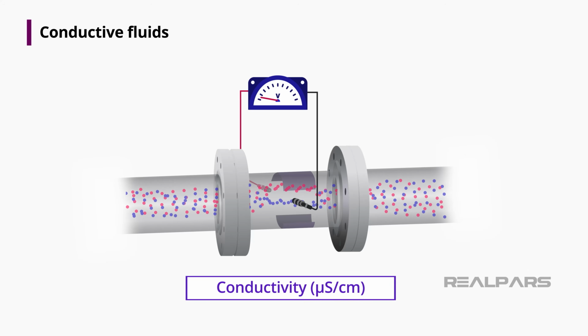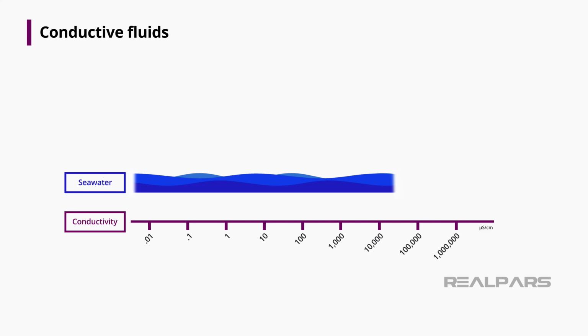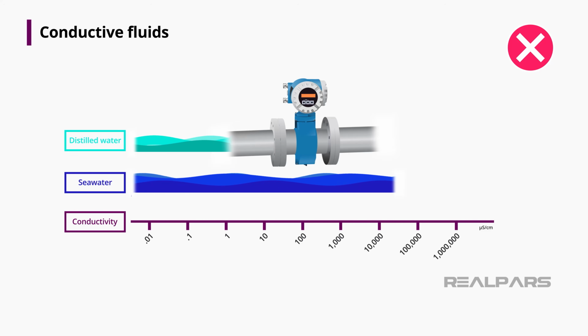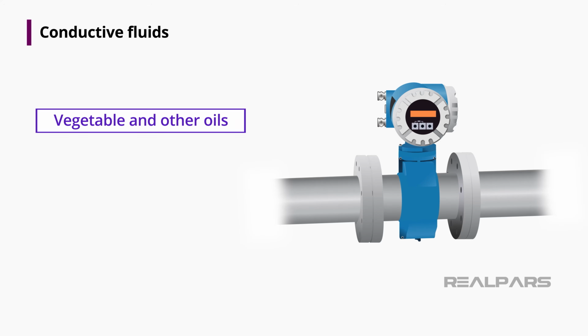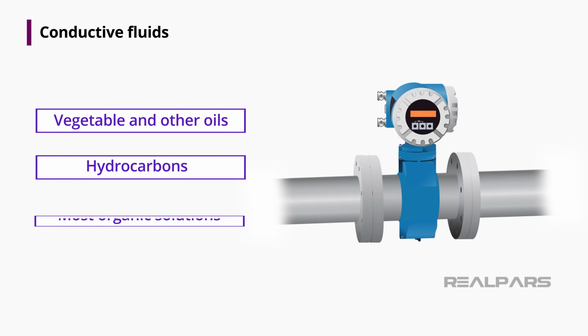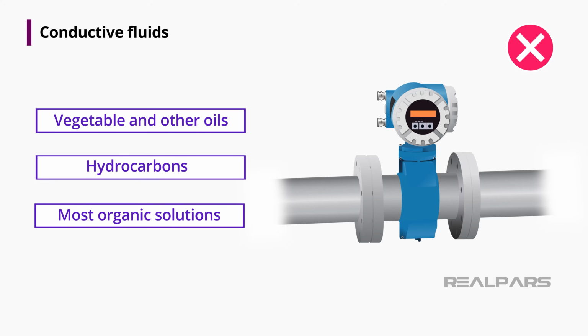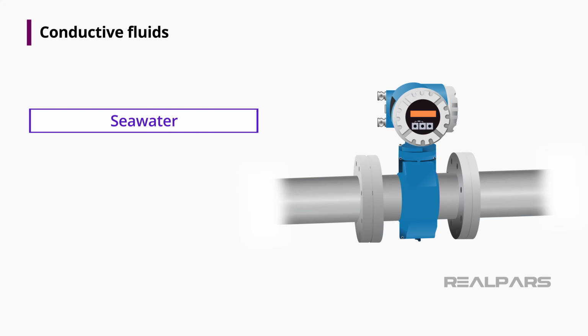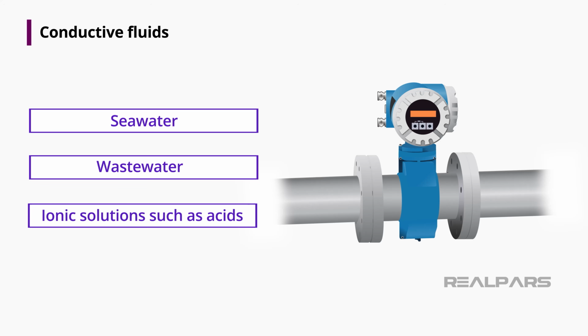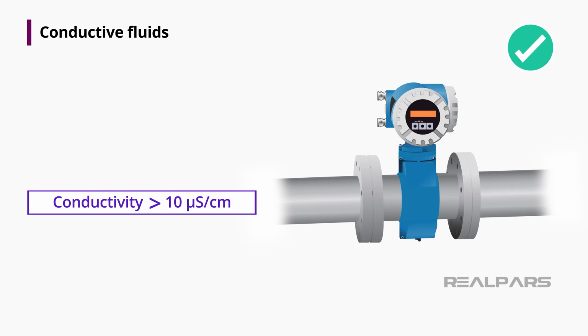The conductivity of liquids is measured in units of microsiemens per centimeter. Some fluids, such as seawater, have high conductivity, and seawater flow can be measured with a mag meter. Distilled water, on the other hand, has a very low conductivity and cannot be measured with a mag meter. Flow rates of vegetable and other oils, hydrocarbons, and most organic solutions cannot be measured with a mag meter. In addition to seawater, flows of wastewater and ionic solutions such as acids can easily be measured by magnetic flow meters. Fluid should have a conductivity of greater than 10 microsiemens per centimeter to be assured of good flow measurements with a mag meter.